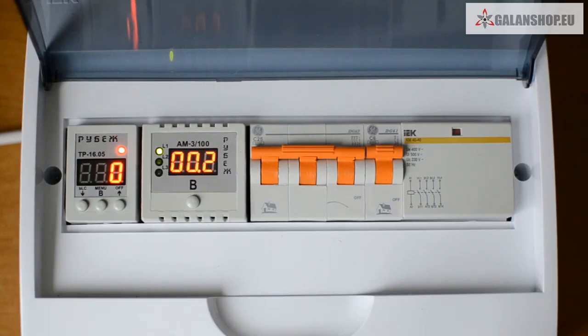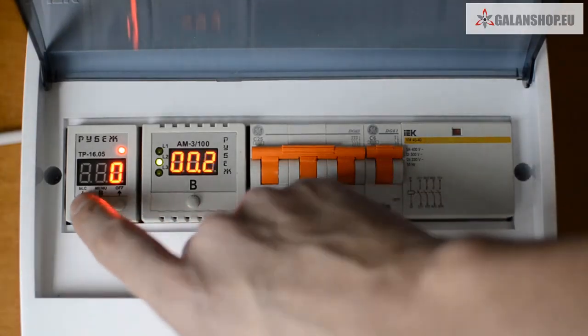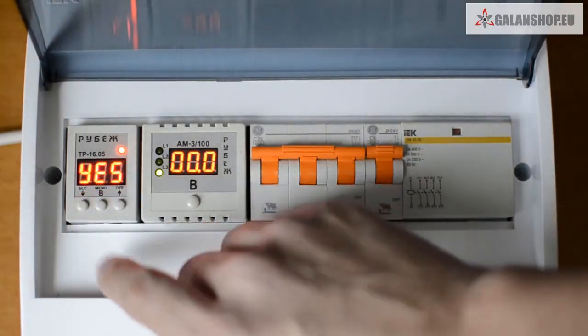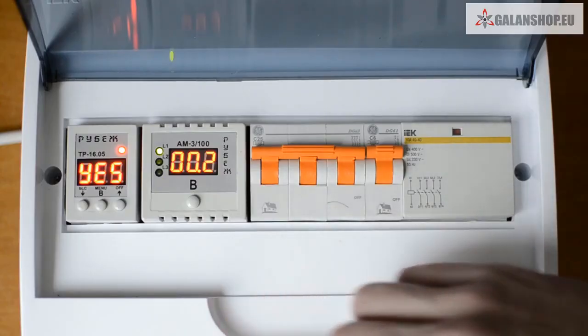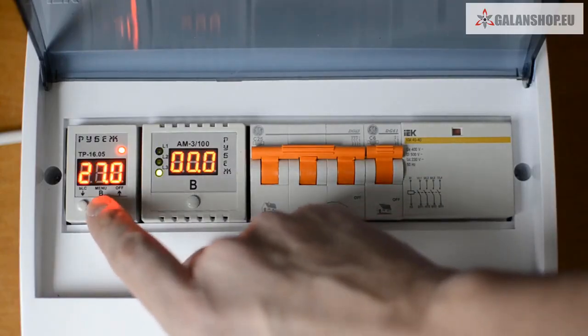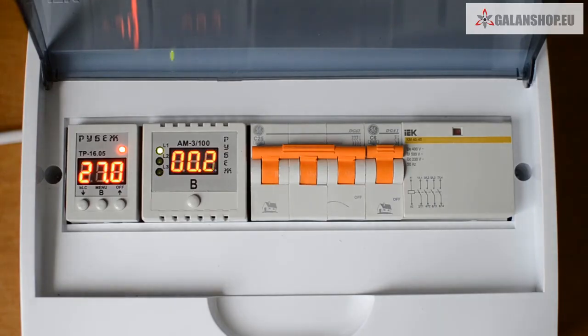The aim of this function is to calculate energy consumed over a certain period of time, for example, over a month. To check or reset the recorded time, you need to enter the heat controller's menu. In order to do it, press the B button and hold it for 2 seconds. Then press the same button shortly and choose a TRE submenu. After that, you can view the recorded time by pressing the up or down buttons. In order to reset the counter, use the down or up buttons to select the yes value and press the B button shortly to confirm your choice under the TRE menu.